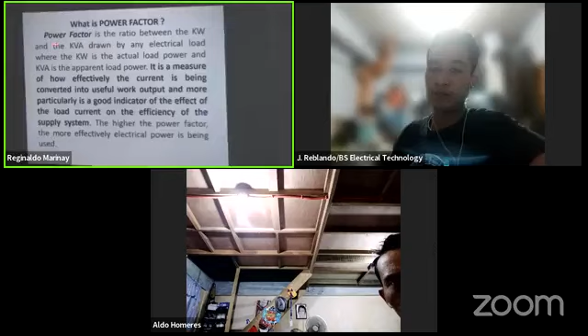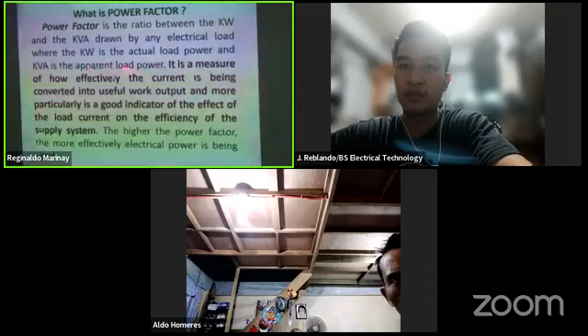What is power factor? Power factor is the ratio between the kilowatt and the kVA drawn by any electrical load, where the kilowatt is the actual load power and the kVA is the apparent load power. Question: what power, basically, are we getting from the utility company, from Meralco, let's say in Manila? Are we getting the kilowatts, the kVA, or the kVAR?